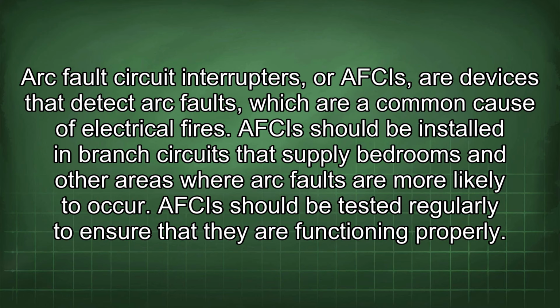Arc fault circuit interrupters, or AFCIs, are devices that detect arc faults, which are a common cause of electrical fires. An AFCI should be installed in branch circuits that supply bedrooms and other areas where arc faults are more likely to occur. AFCIs should be tested regularly to ensure that they are functioning properly.